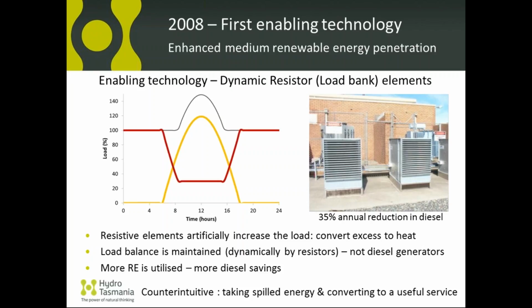That seems counterintuitive as to why it would benefit the system. But as you can see in this idealised graph, by introducing that load we allow the renewables to contribute their maximum output. The distinction is that the load can be controlled very accurately and quickly, and by controlling it we obtain an ancillary service from that renewable generation. In this case, we use it for frequency control of the entire island system, a job normally done by diesel engines. So we've transferred that job to the renewables, saving further diesel consumption, and it also protects the diesels from going into reverse power mode.